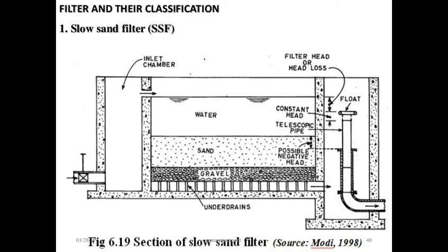So what you have to do? You have to open this valve. The water will enter from this portion to the inlet chamber. It will be filled with water, this inlet chamber. From the inlet chamber the water goes to the filter media, sand. From sand to gravel, gravel to the under drain pipes.